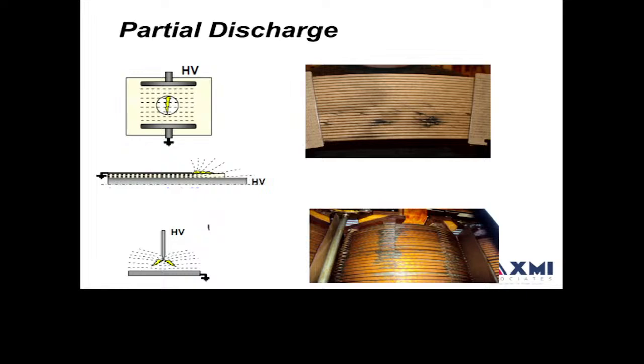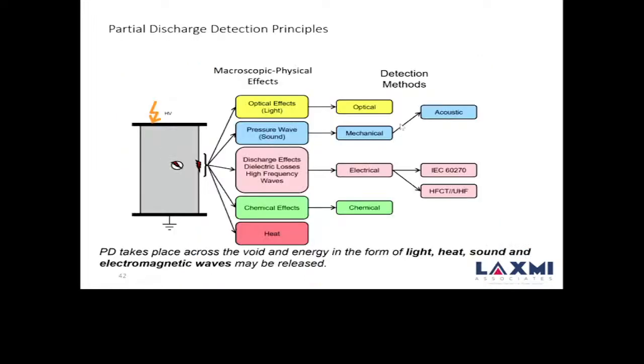So partial discharge means you have an insulation, but part of the insulation starts conducting because of a weakness in the insulation. It has some contamination, moisture or some cavity, so it starts having some conduction in between. Insulation as such should not conduct, but you have some such spots and it starts conducting. This is an internal discharge, this is a surface discharge across the surface. This is internal because it is happening inside the insulation, and this is the corona, which is just surface tracking. These kinds of partial discharge patterns could be found in transformers. Some of the photos are here. You can see this is a surface discharge, this is a kind of internal and surface discharge mix.